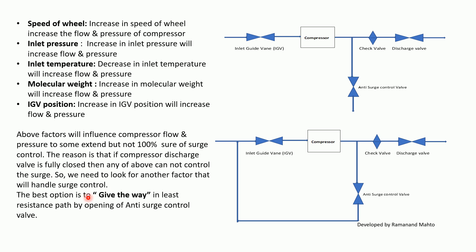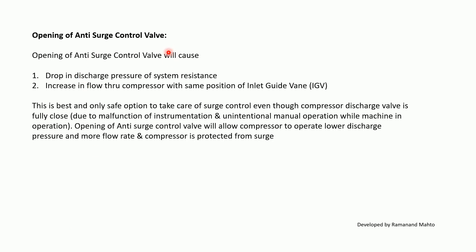The best option is to provide the least resistant path by opening the anti-surge control valve. Opening the anti-surge control valve allows more flow through the compressor and reduces discharge pressure. Opening the anti-surge control valve causes a drop in discharge pressure, increasing the flow through the compressor with the same IGV position. This is the best and only safe option to handle surge control, even when the compressor discharge valve is fully closed — whether closed due to instrumentation malfunction or unintentional manual closure. Opening the anti-surge control valve allows the compressor to operate at lower discharge pressure and higher flow rate, protecting it from surge.